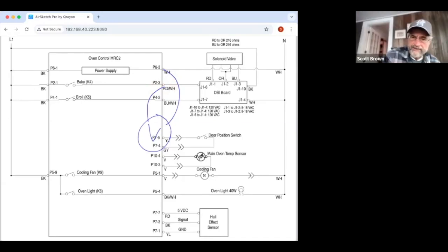You guys familiar with black box troubleshooting? This is how they taught us in the Navy. So we got a black box and it's got all kinds of weird stuff in it, but we don't care - it's not putting out something, so what's the logical troubleshooting response? If you got a black box, say the DSI board, just treat it like a black box, just a box with some numbers and letters on it, and we don't really care what's going on in there for the purpose of what I'm trying to illustrate here. So it's not putting out anything - you're not getting spark, it's not trying to open the valve. Just in black box troubleshooting, you go, okay, my black box isn't putting out outputs, but I know I need inputs for that black box to put out outputs.